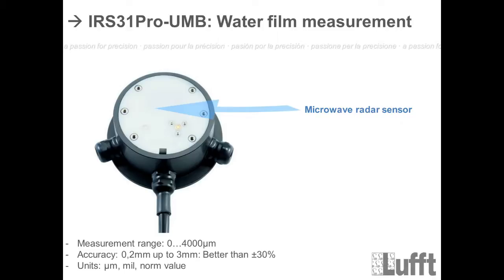The next measurement is the water film. The water film measurement is done with a microwave radar sensor under the surface in the middle of the sensor. The measurement range is the same as the IRS 31 — between zero and 4,000 micrometers, with accuracy of 0.2 millimeters up to three millimeters, better than plus/minus 30 percent. Units are micrometers, mils, and norm value.